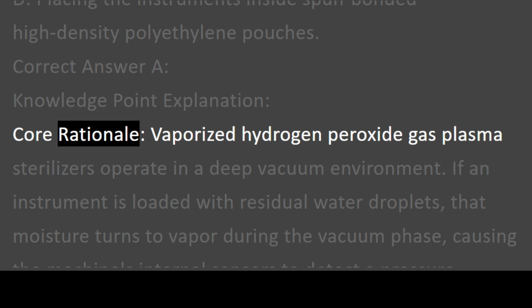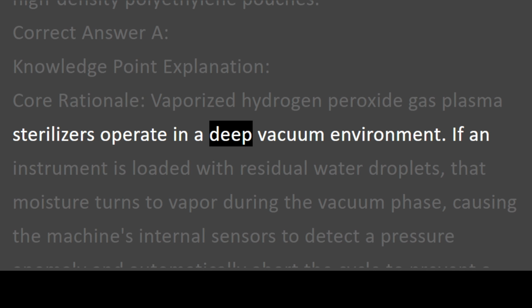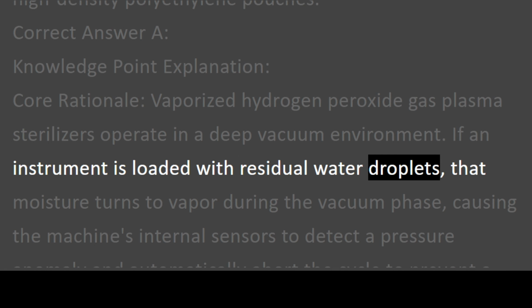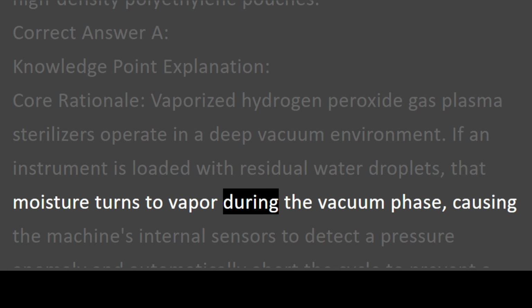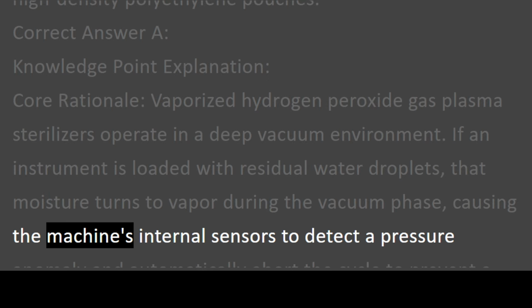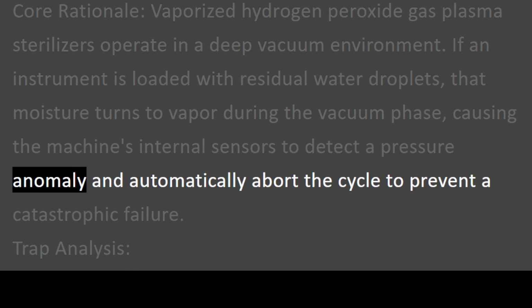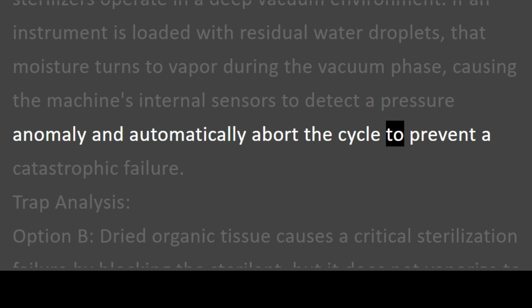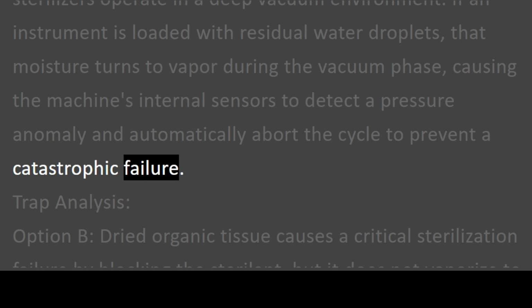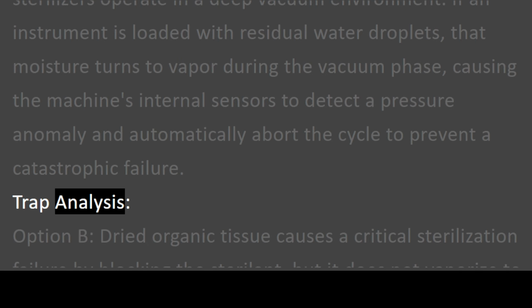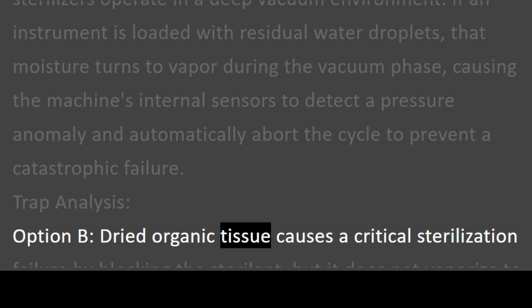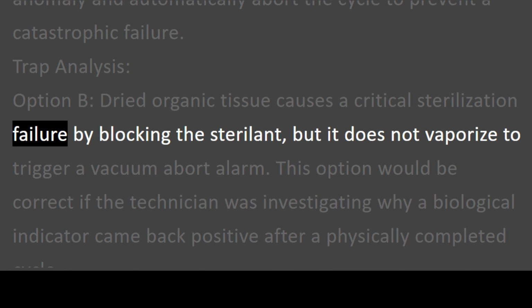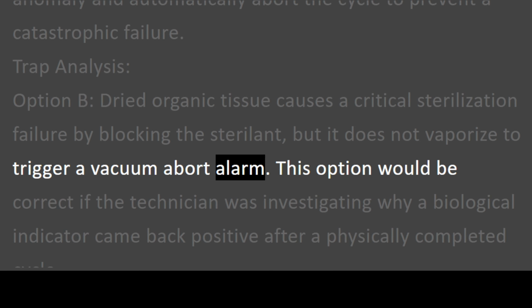Core rationale. Vaporized hydrogen peroxide gas plasma sterilizers operate in a deep vacuum environment. If an instrument is loaded with residual water droplets, that moisture turns to vapor during the vacuum phase, causing the machine's internal sensors to detect a pressure anomaly and automatically abort the cycle to prevent a catastrophic failure. Trap analysis. Option B, dried organic tissue causes a critical sterilization failure by blocking the sterilant, but it does not vaporize to trigger a vacuum abort alarm.